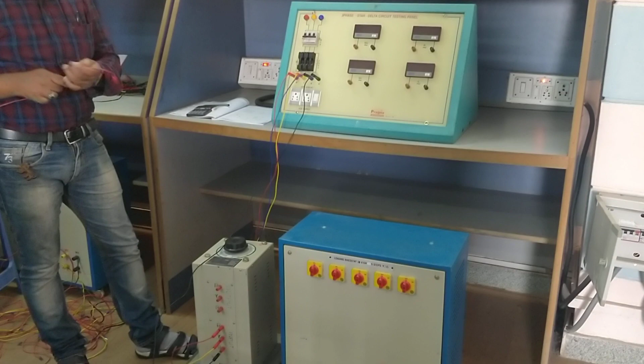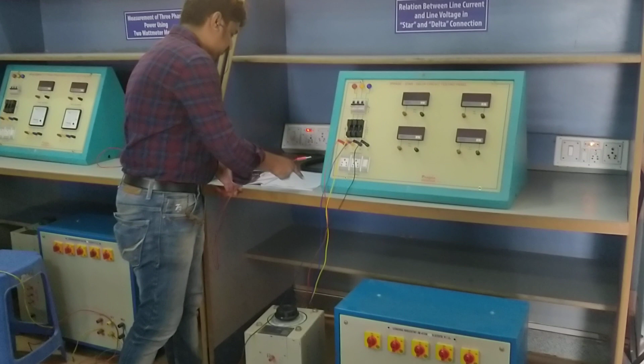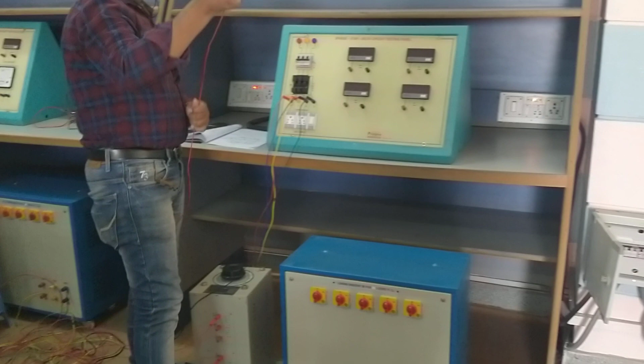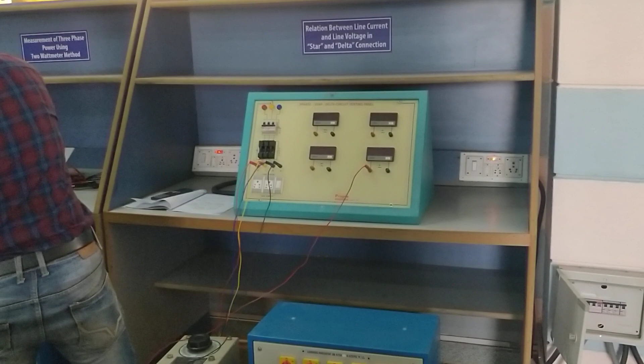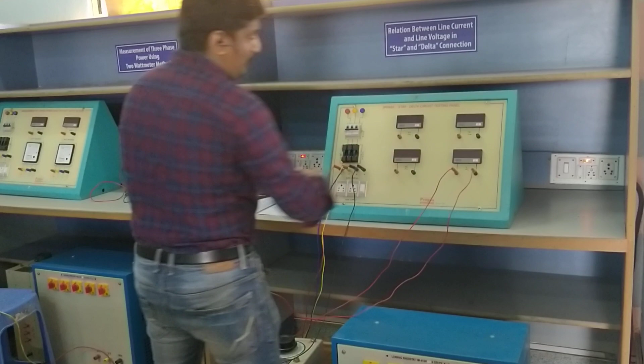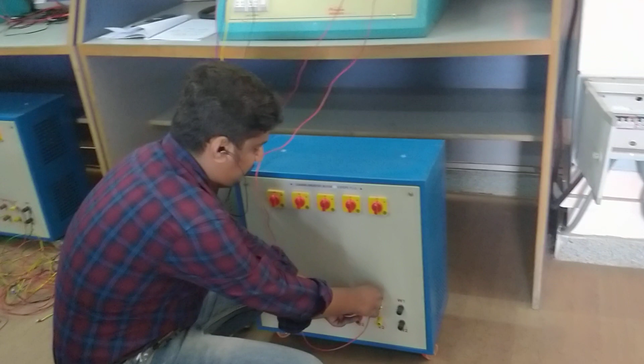Now we start with the output connection of the auto transformer. From R, it should go to the line ammeter using a long wire. The voltmeter will be connected later. The other end of the ammeter, since it runs between lines, should go to U1, which is the top of the resistive load: U1, V1, W1, U2, V2, W2.